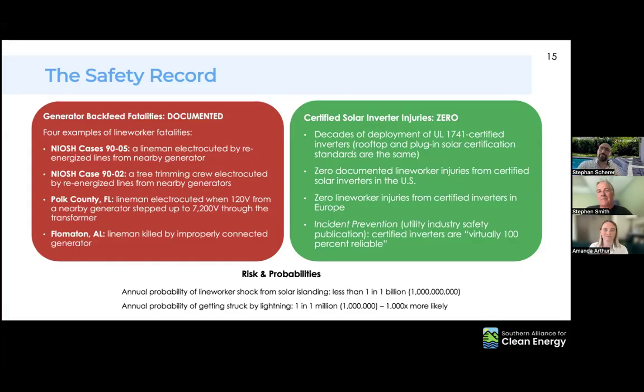On my first slide, I showed the transformer on the left in the picture, where the cables go into the house. That transformer can do two things: it can take high voltage power and step it down to 240 to 120 volts for your home, or it could do it in reverse. It doesn't differentiate. So when you plug in a generator, typically through what we call a suicide cord—because it's so dangerous—essentially from an outlet on the generator to an outlet in your home, without a transfer switch to ensure that when the grid is down it doesn't power the grid, that voltage gets amplified to thousands of volts. And that's what can kill and has killed line workers.